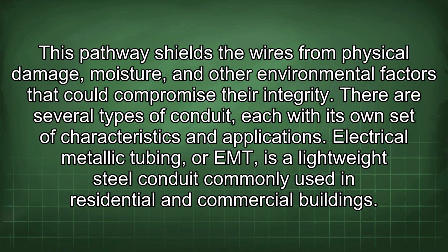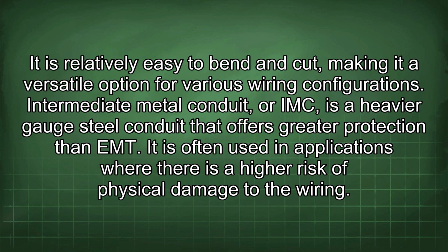There are several types of conduit, each with its own set of characteristics and applications. Electrical metallic tubing, or EMT, is a lightweight steel conduit commonly used in residential and commercial buildings. It is relatively easy to bend and cut, making it a versatile option for various wiring configurations. Intermediate metal conduit, or IMC, is a heavier gauge steel conduit that offers greater protection than EMT.